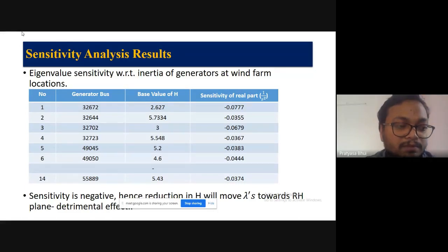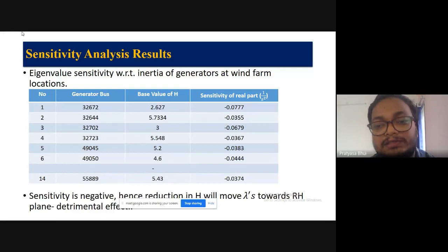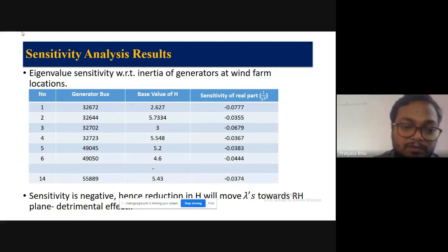But when we add renewables, we don't increase H or inertia, we just reduce inertia. That means it will have the opposite impact. So if you reduce the inertia, your eigenvalue real part will go towards the positive half plane. So your damping ratio will reduce and your damping will become poor. So it will have a detrimental effect.